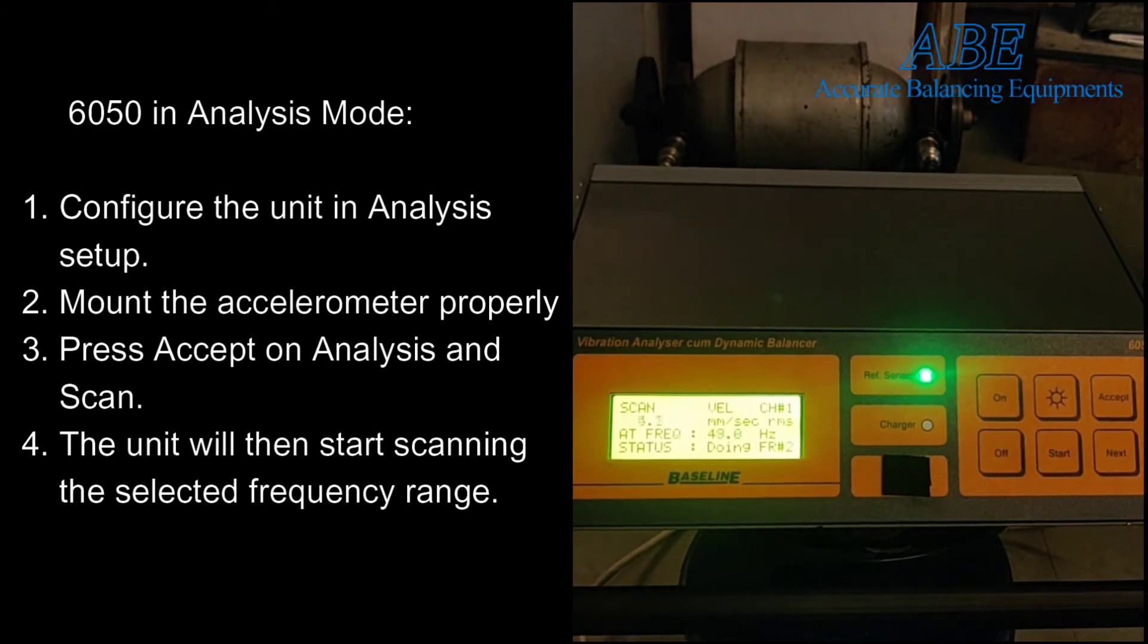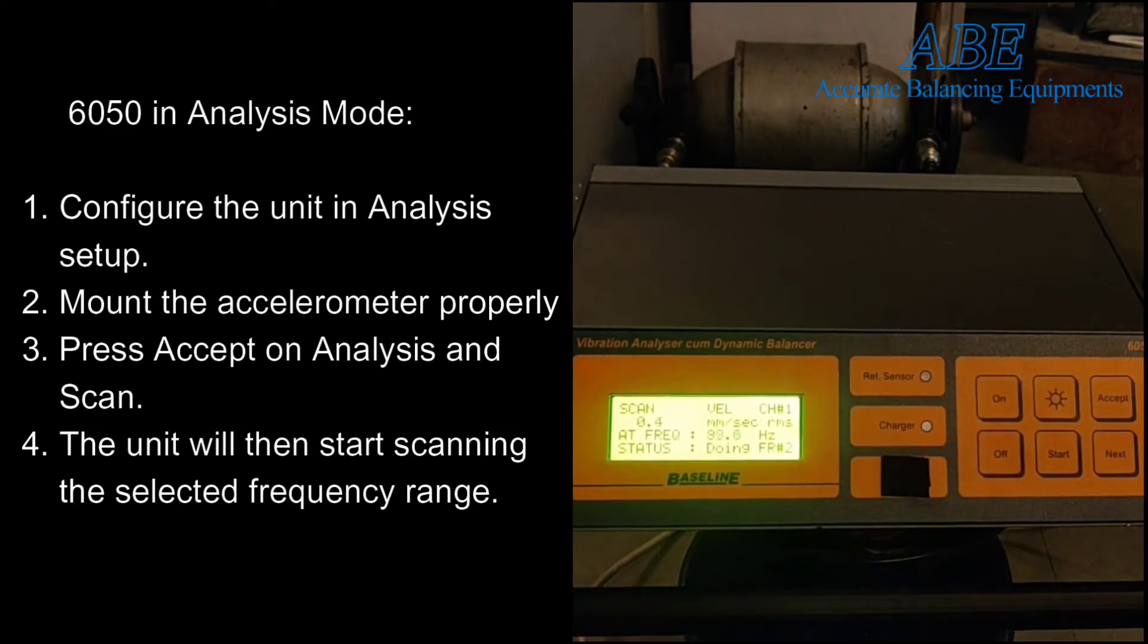If imbalance is the dominant cause of vibration, a peak will be found at the rotational frequency with a magnitude comparable to the overall vibration. With the PC software Vs22, developed by Baseline Technologies and supplied with the 6050, the spectra can be quickly transferred to the PC over serial port where the spectra can not only be saved and printed on the PC.